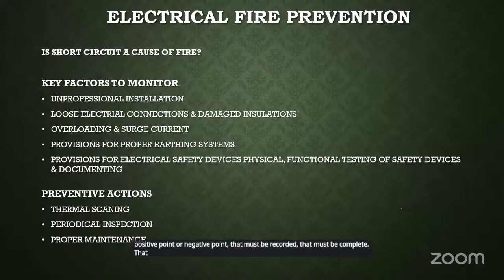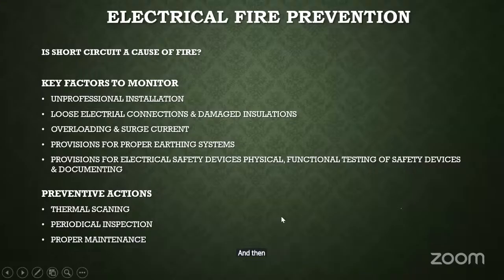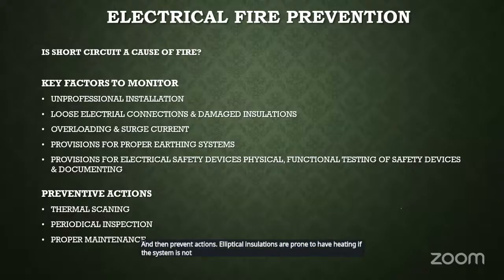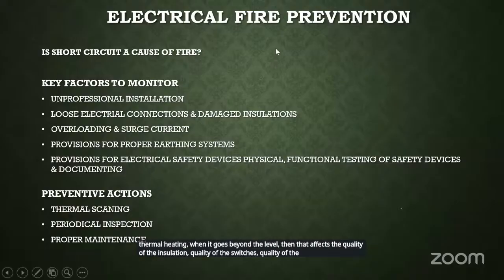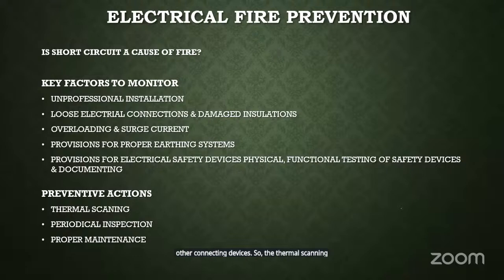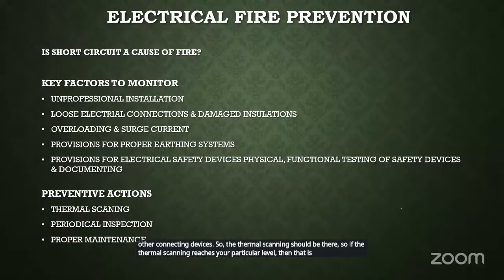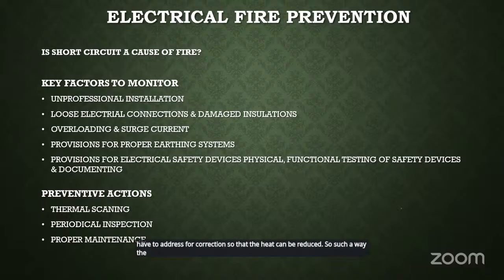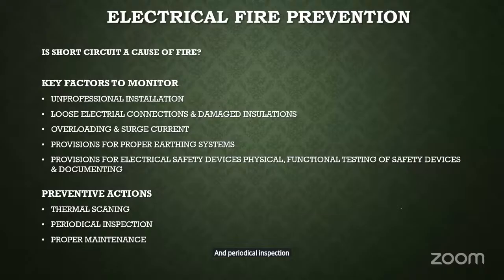That is documentation. And then preventive actions: electrical installations are prone to heating if the system is not properly designed or is overloaded or due to some other factors. When thermal heating goes beyond the level, it affects the quality of the installation, the switches, and the other connecting devices. So thermal scanning should be there. If the thermal scanning reaches a particular level, that is the point you have to address for correction so that the heat can reduce. So thermal scanning, periodical inspection and proper maintenance must be there so that you can prevent electrical fire.